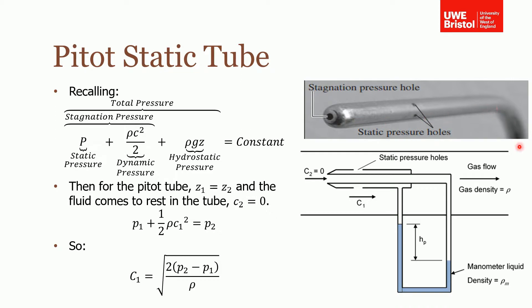You can see it's a tube bent with a 90 degree bend, and what it is is effectively a pipe within a pipe. You can see this hole on the center line here, and on the outside you can see these so-called static pressure holes. If you look at the schematic, you can see that the center hole or tube goes all the way around and connects to one side of the manometer. Then this outer tube with the static pressure holes, this kind of sleeve, is all connected to the other end of the manometer.